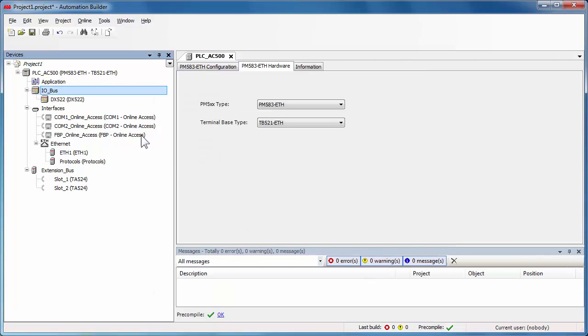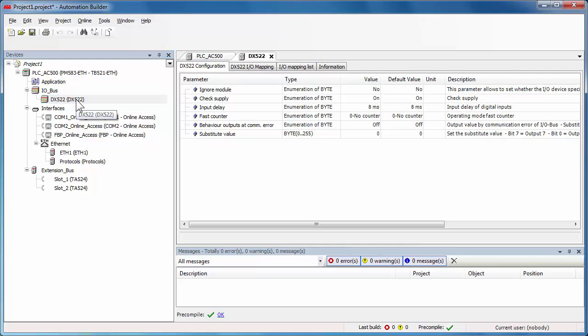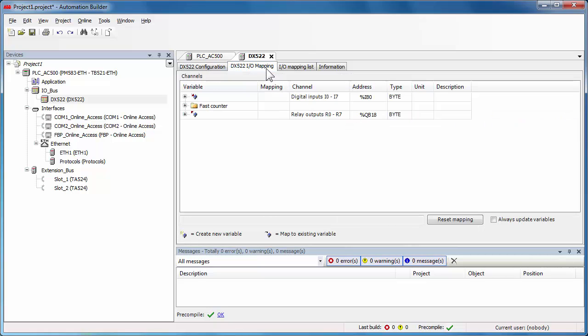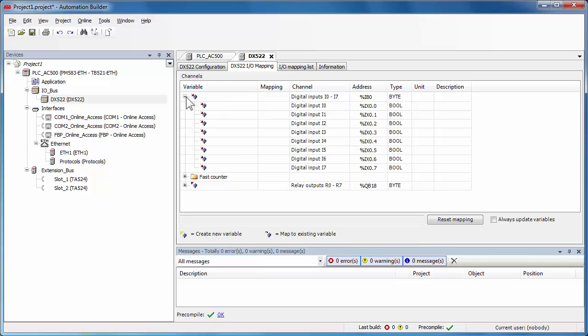Automatically, an editor window will be associated to the IO module to be able to configure the module and its channels using defined parameters, and then map its inputs and outputs using the IO mapping tab. All available IO channels get automatically an IO address.